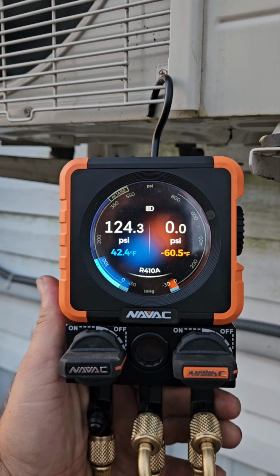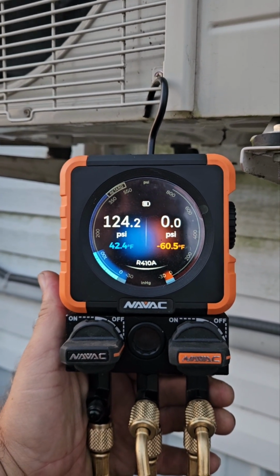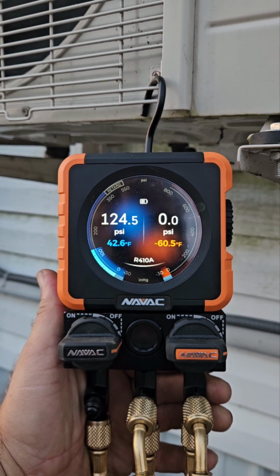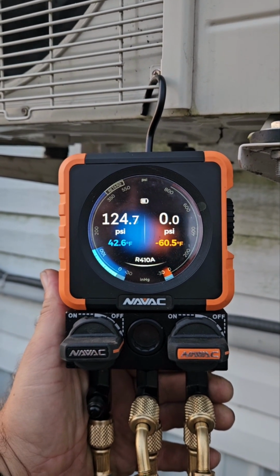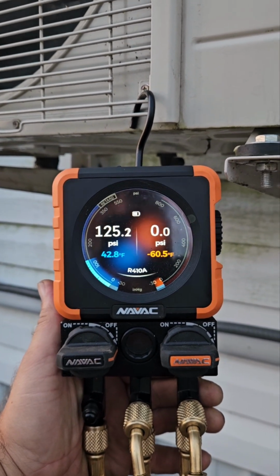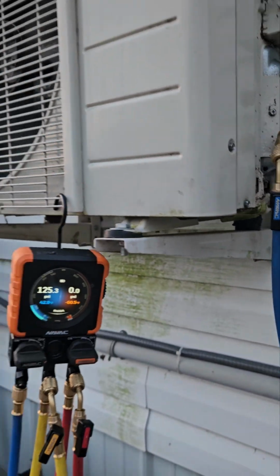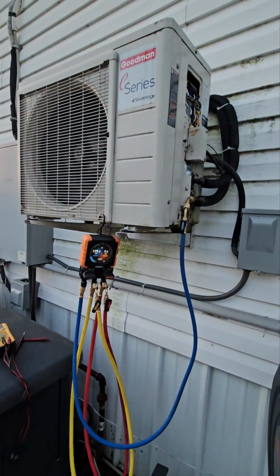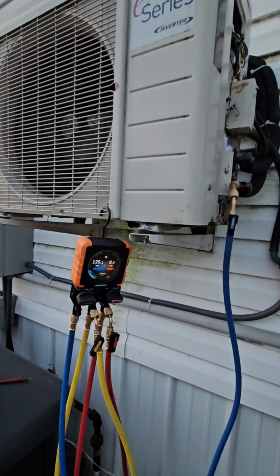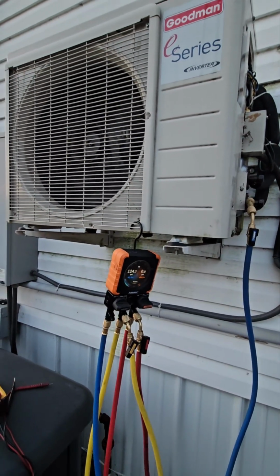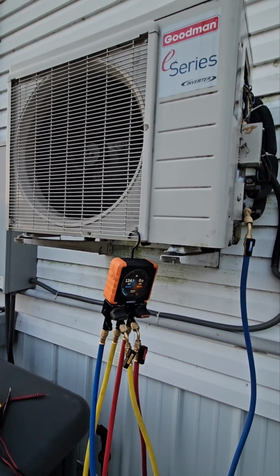124 on the pressure on the low side, down at 42.6 to 42.4 temp there. So that shouldn't be freezing up at that point. Everything's looking good at this rate. We'll just have to see here. Time will tell, I think it might have ran a couple hours last night before it aired out again.